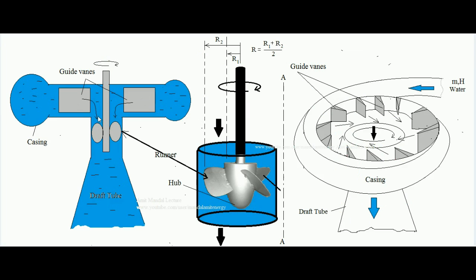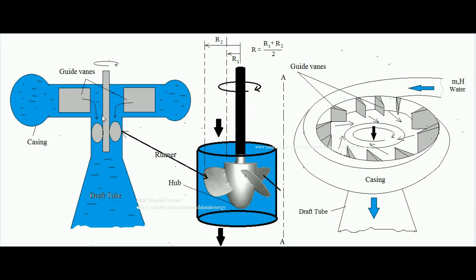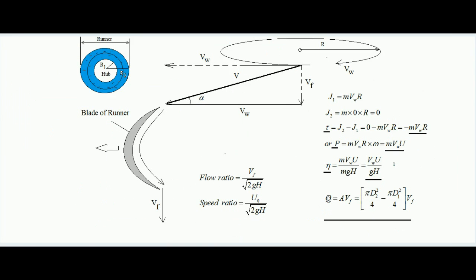For efficiency: when water enters and interacts with the runner it carries a head H. The input energy is m·g·H — to convert head into energy we multiply by mg. The output is m·Vw·u. Therefore hydraulic efficiency equals output divided by input: m·Vw·u divided by m·g·H. Cancelling m, the hydraulic efficiency of the Kaplan turbine is Vw·u divided by g·H.